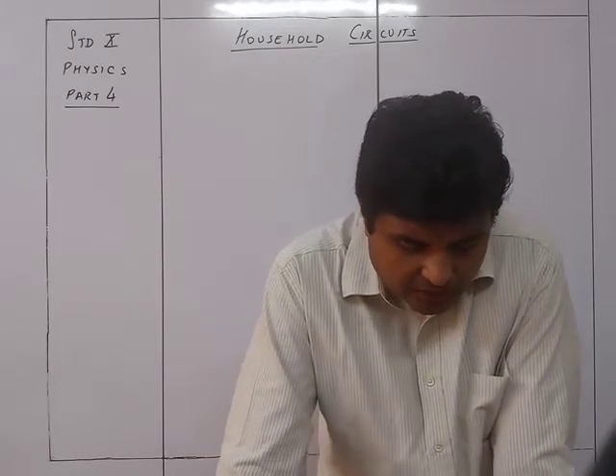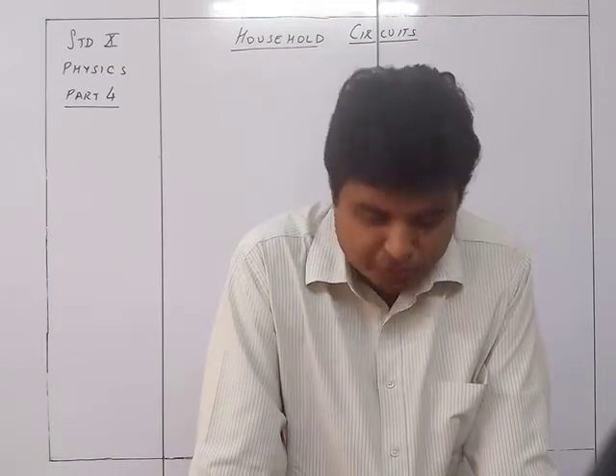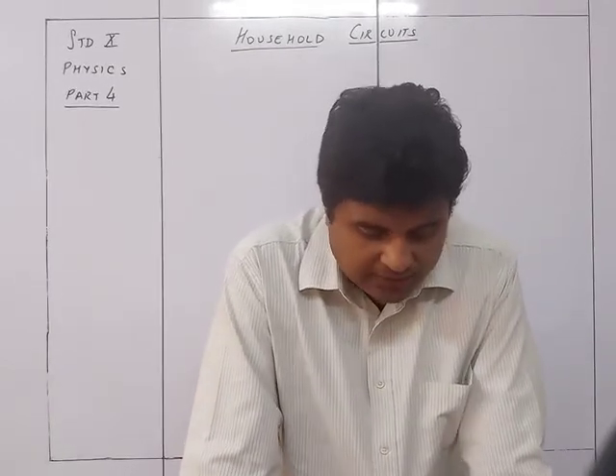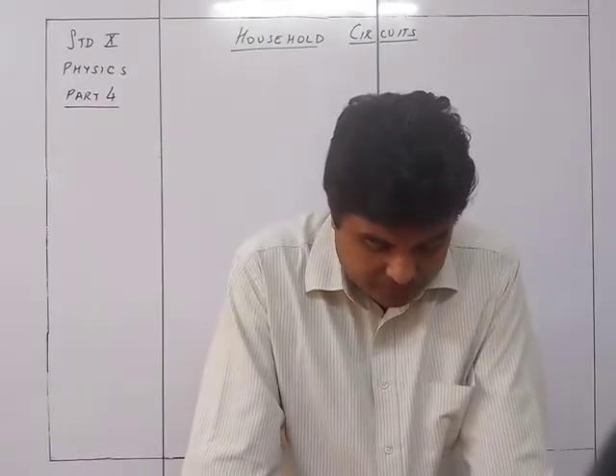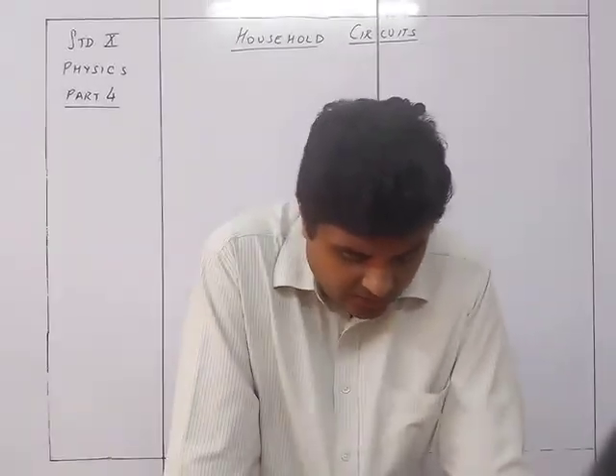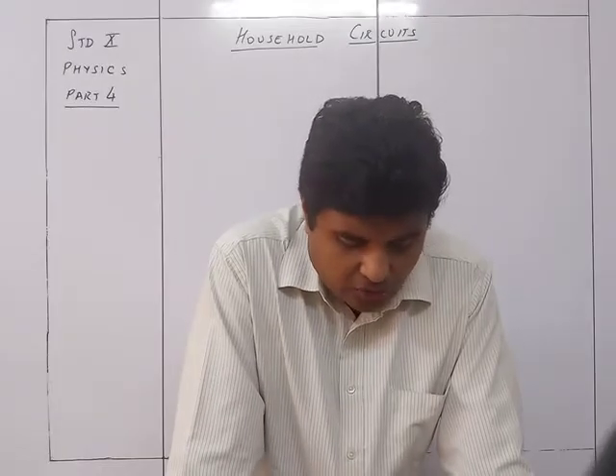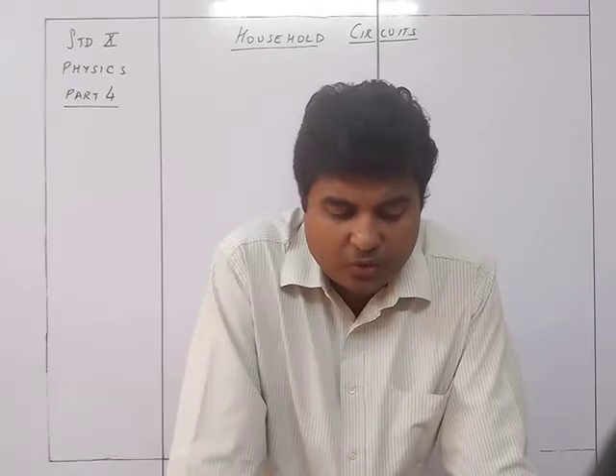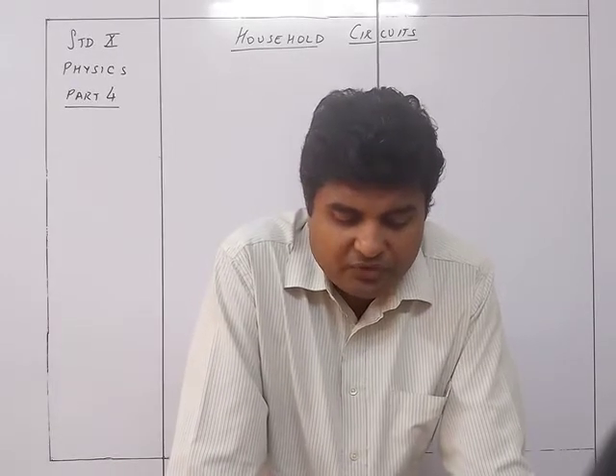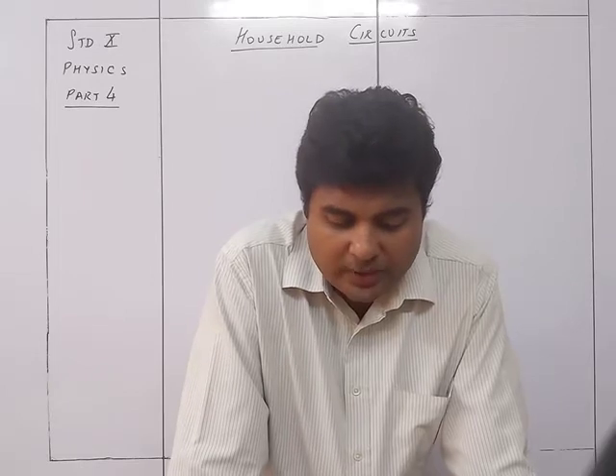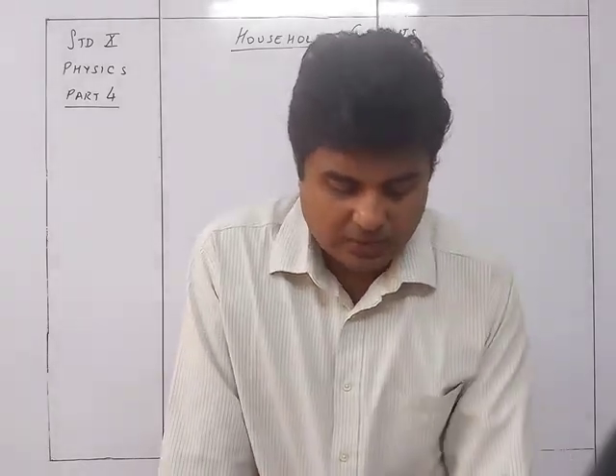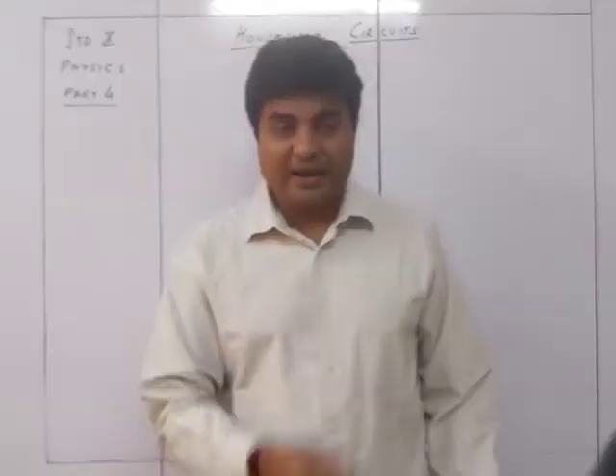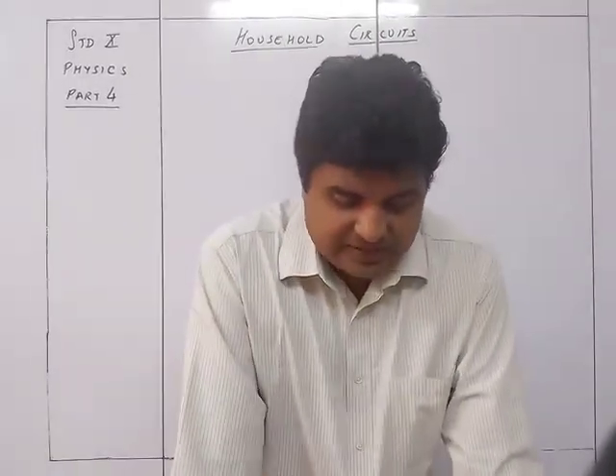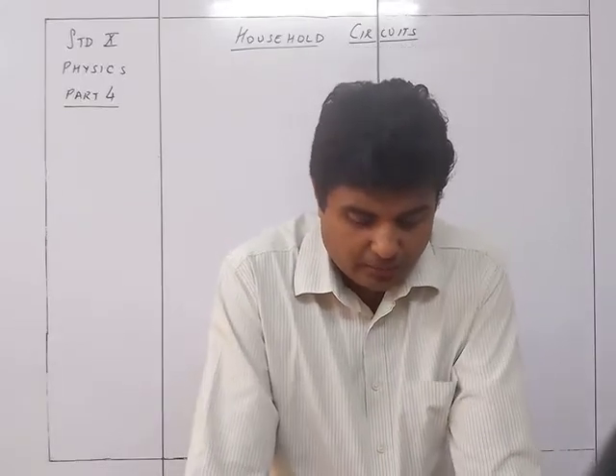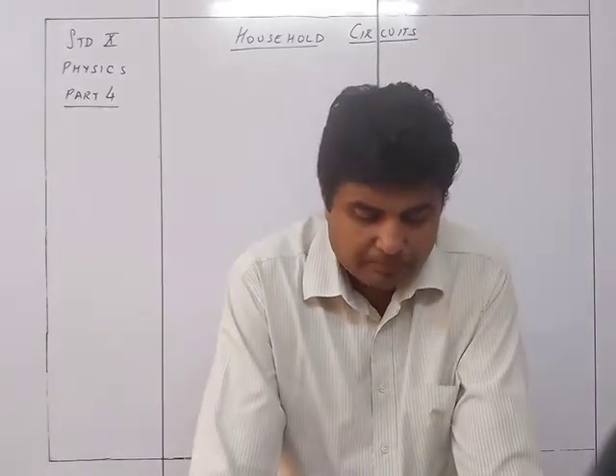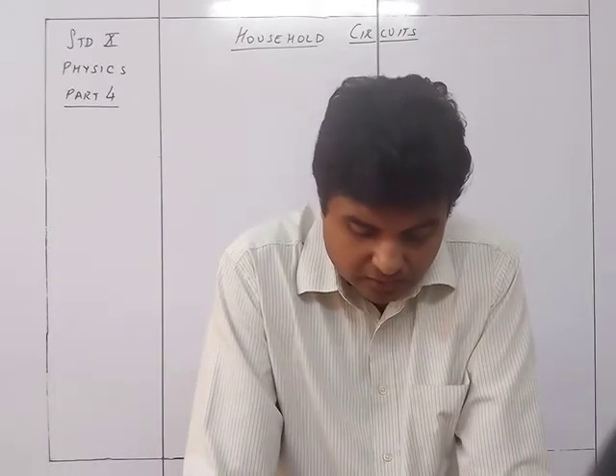We have read that local earthing is done in the house near the kWh meter. For this purpose, a hole nearly 2 to 3 meters deep is dug in the ground. A copper rod or a thick copper wire covered by a hollow insulating pipe is inserted in the hole. A thick copper plate of dimension 50 cm by 50 cm is welded at the lower end of the copper rod and is buried inside the ground as shown in figure 9.22. The place is surrounded by a mixture of charcoal and salt to make a good contact between the plate and the ground and the earth.